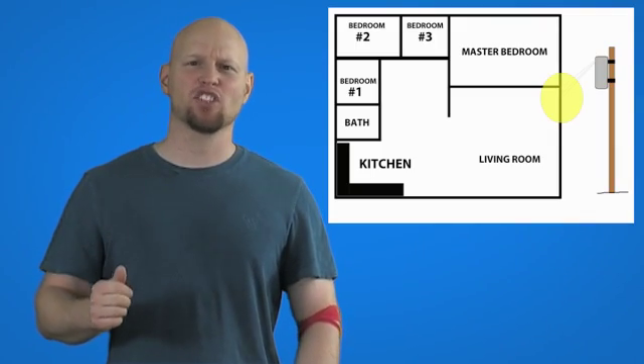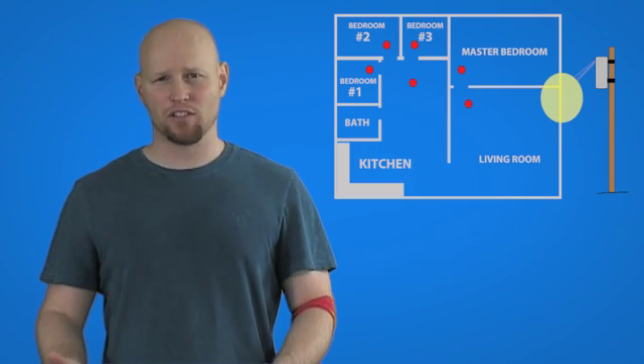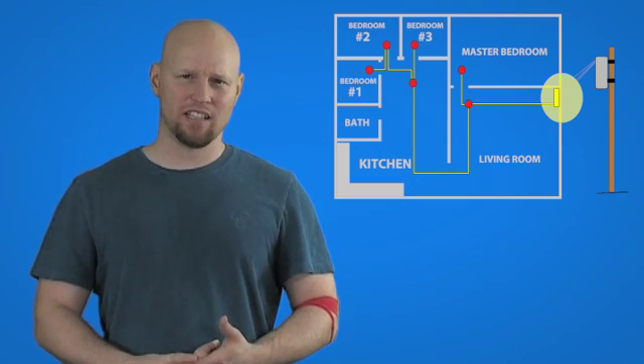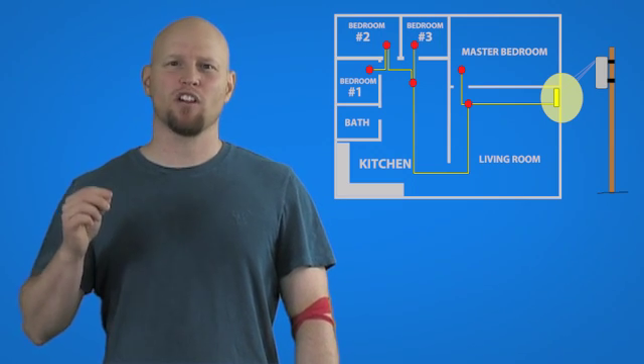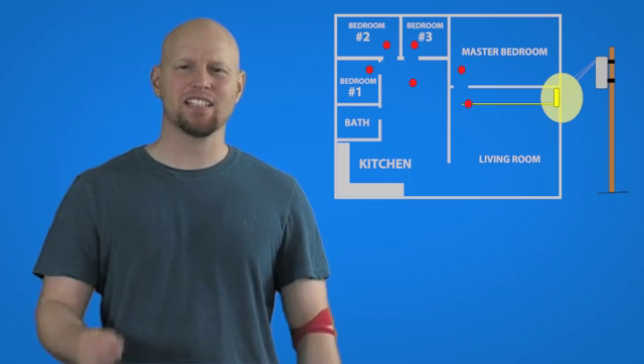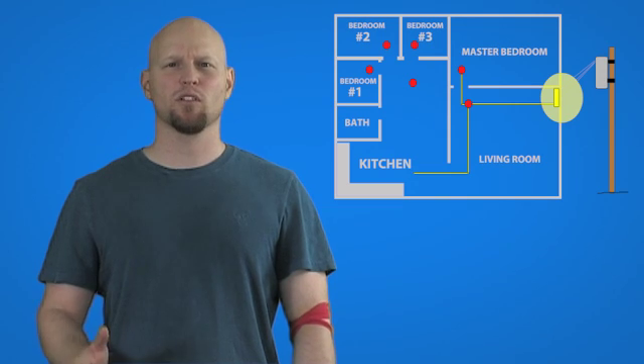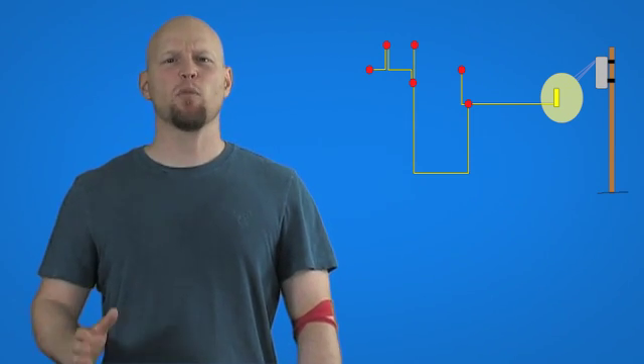This is considered an interconnected or hardwired system. An interconnected system is better because all smoke alarms receive their power from the home's electrical service, and every alarm is connected not only to the electrical power but also to the other smoke alarms. This means if a single alarm detects smoke, not only that alarm but all of the other smoke alarms in the house will sound as well.